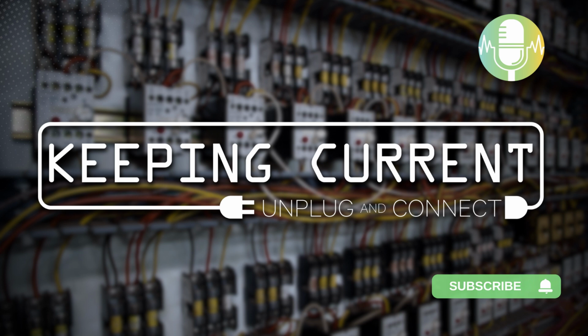When you wait for the 5-year update, you really haven't documented the changes that happened to your system, and maybe the person responsible for implementing that update is no longer with the company. I hear a lot of people say nothing has changed in their electrical system, but that might be true for the physical system itself, it's the things you can't see. Has available fault current changed? Has somebody gone in and changed a setting temporarily on an interrupting device because of a nuisance outage? Has available fault current increased such that some breakers that would have interrupted a fault before will no longer do that?